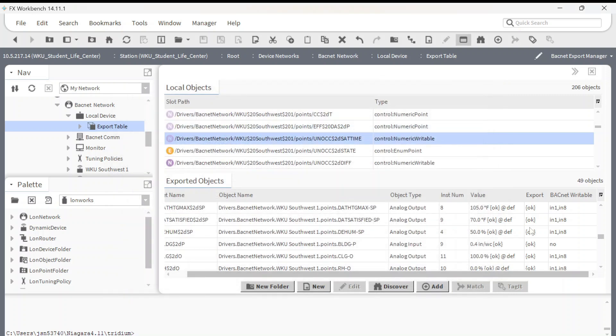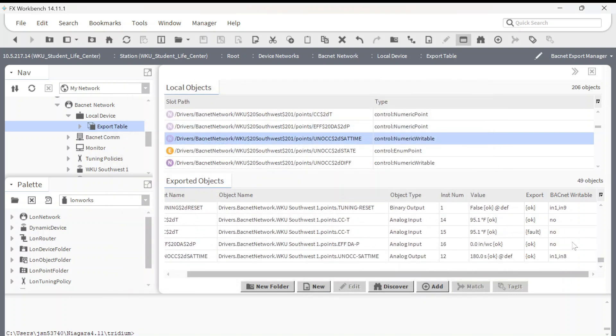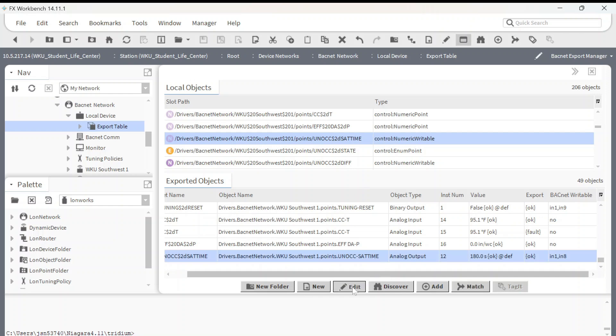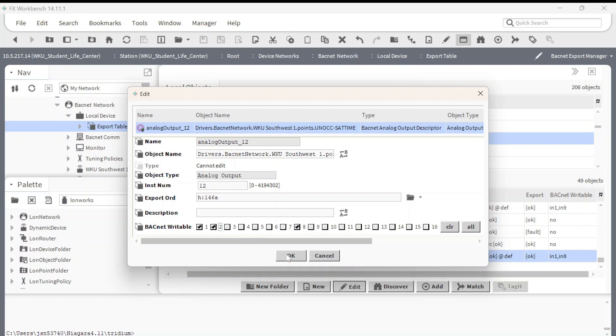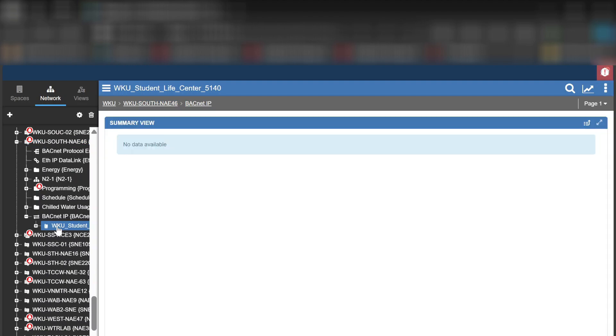Regardless of whether it is an analog, binary, enumerated, or whatever — if you don't change that to an output, it's not going to let you do anything with it. You'll need to select a couple of the priorities and you can come back and edit these later in the export tables. I would highly recommend that for any points you are going to pull in as writable, you take the time to go through this step. Technicians often grab all the points, drag them in, and then later someone tries to make an adjustment and cannot — because the points were not pulled in properly.